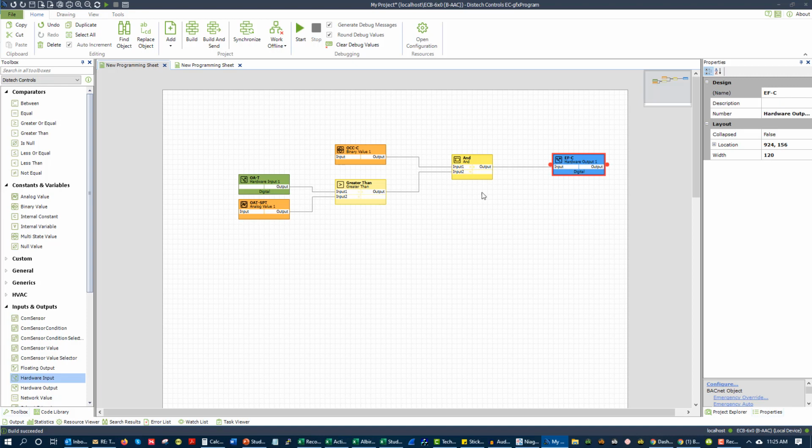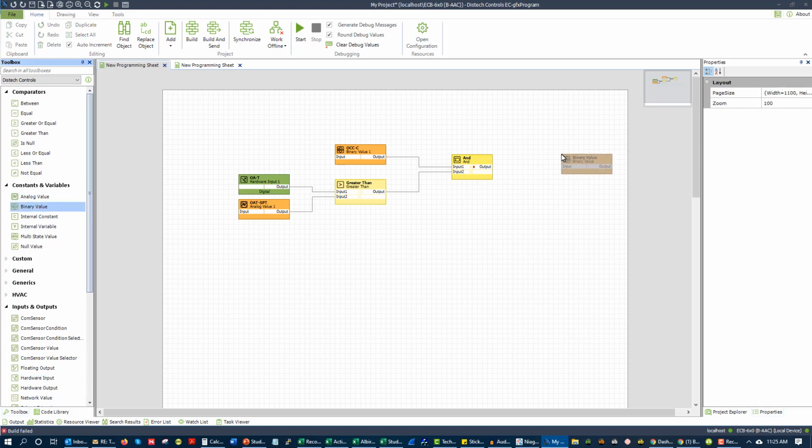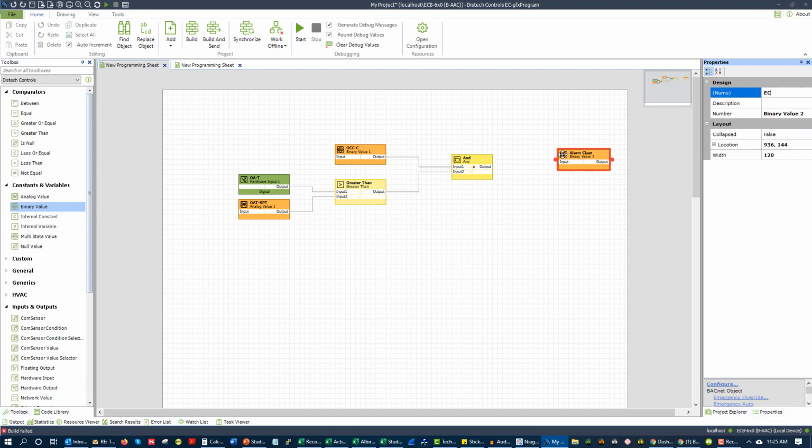Sometimes a control mode is actually logical, and maybe we have this and it's called economizer enable. This is a point that we're going to use in our program in order to do economizer enable. So this would be a binary logical point that this kind of control mode is driving.